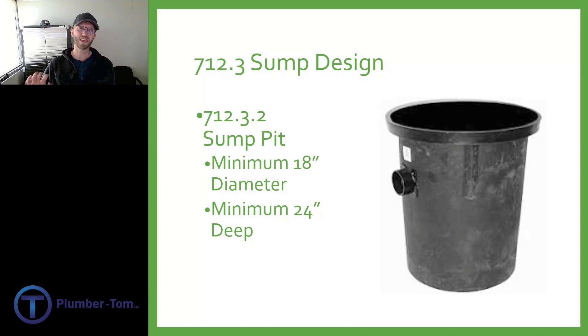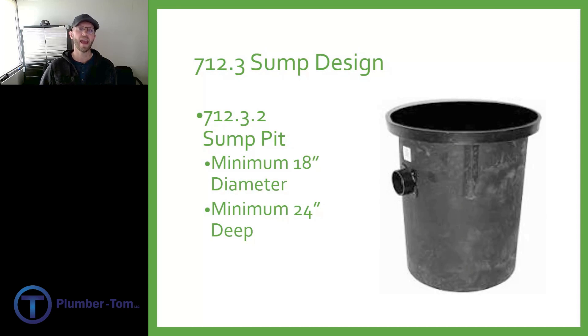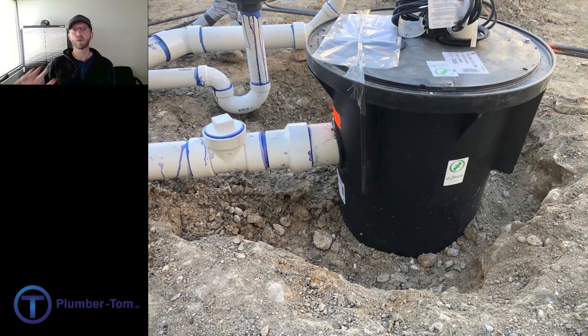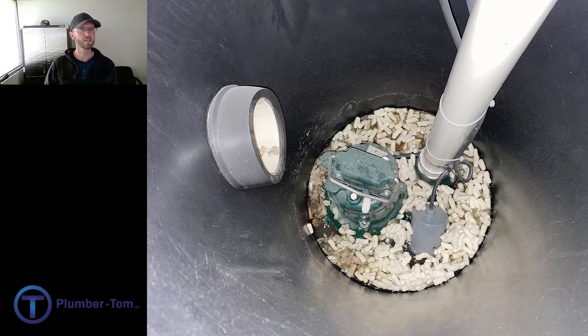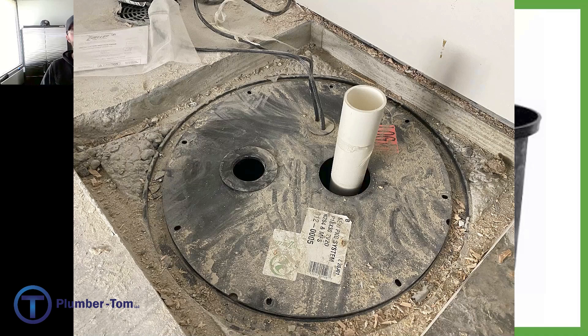712.3 covers sump design, stating that the sump pit itself must be at least 18 inches in diameter and 24 inches deep — those are the minimums. You can buy great kits for this from companies like Liberty Pumps or Little Giant, getting the whole system with the sump, the pump, and connection points ready to drop in the ground.